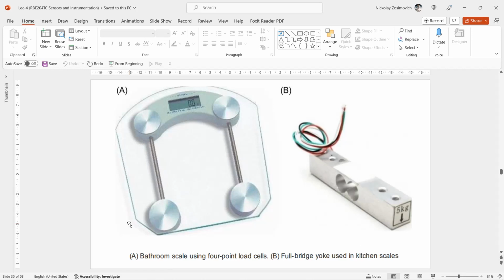A typical example is found in bathroom scales, where four yokes are mounted at the corners of a plate, each containing two strain gauges in half-bridge configuration, as you can see in this figure. These four half bridges are connected into a full bridge configuration, thereby summing the individual contributions to the total weight of the person standing on the plate. In kitchen scales, on the other hand, as you can see here, typically one yoke with a full bridge configuration is used.